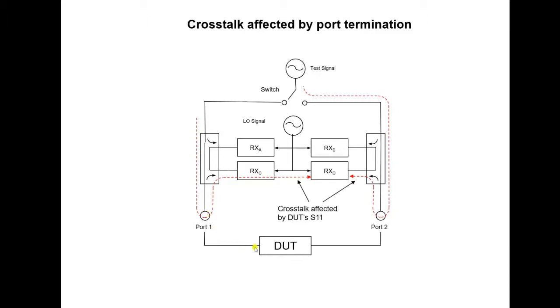As the test signal hits the device under test, some of it will get reflected back, obviously into this receiver here, but because of imperfections, some of that signal will leak through to the other side and appear as crosstalk. This crosstalk component will depend on the match of the device under test, the S11 of the DUT.